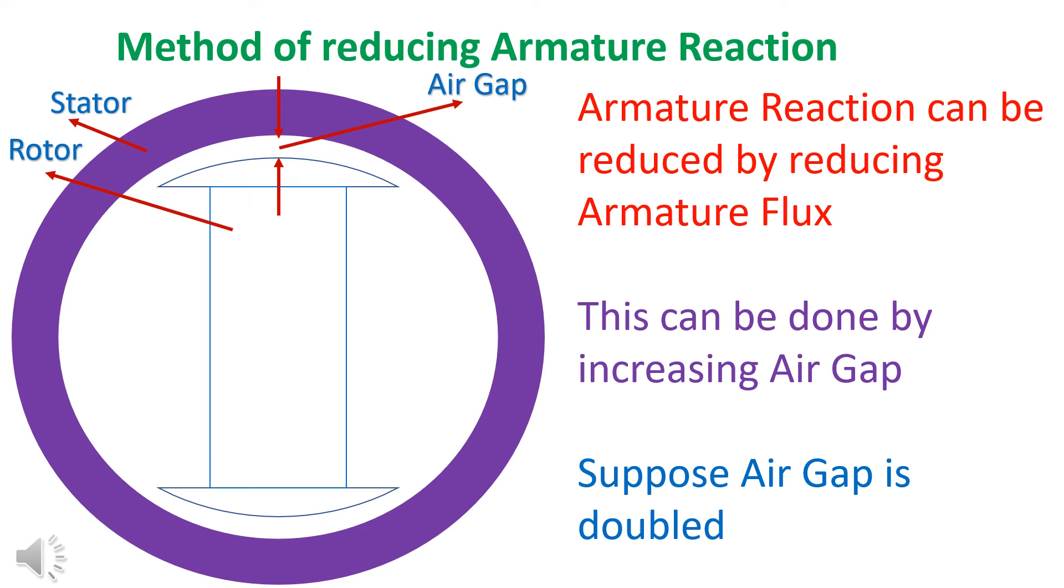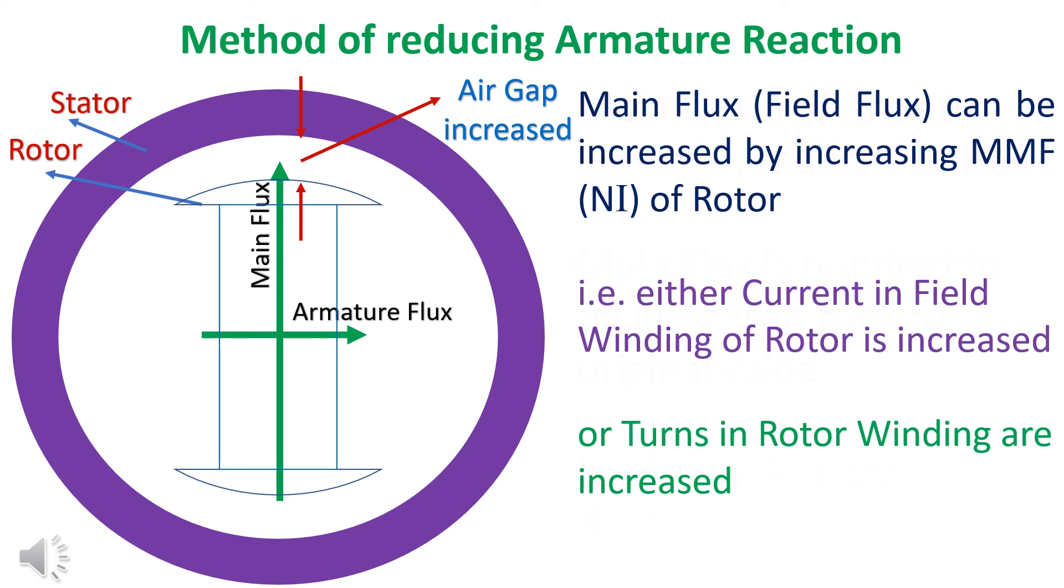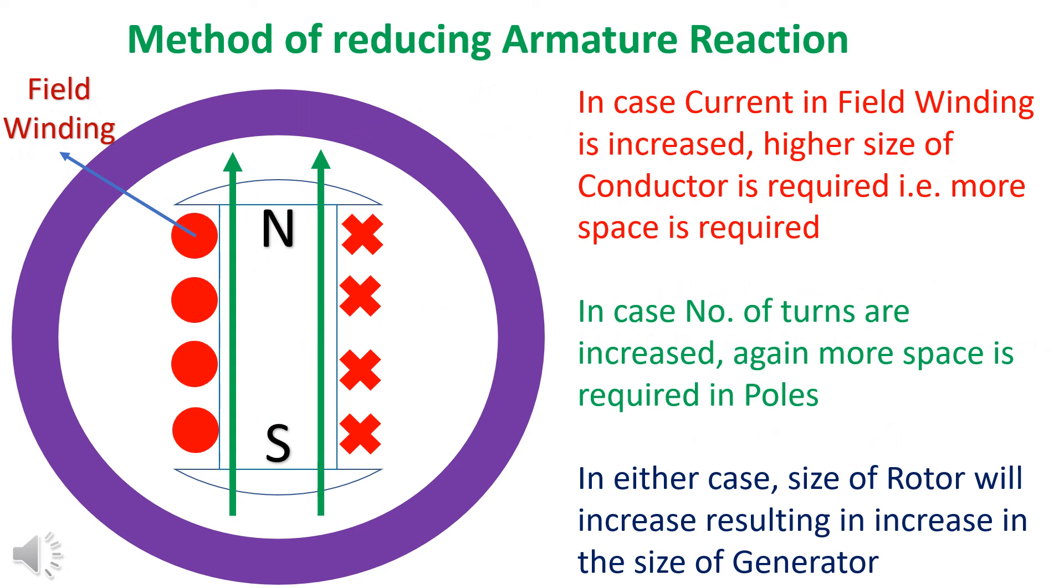Armature reaction can be reduced by increasing air gap. But main flux also reduces. Main flux is required to be increased to obtain the required EMF. Main flux can be increased by either increasing field current or number of turns in the rotor. In either case, size of rotor increases, resulting in increase in the size of the generator.